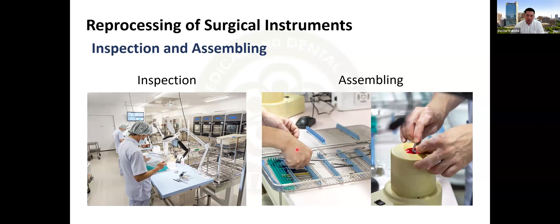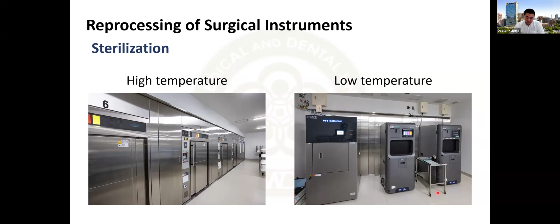Packaged instruments are sterilized in a sterilizer. Sterilization methods include high temperature and low temperature. The sterilization method is selected based on the instrument instruction for use, taking into consideration the characteristics of the instrument and its compatibility with the sterilant. In our hospital, hydrogen peroxide gas plasma sterilization and low temperature steam formaldehyde sterilization are used for low temperature sterilization.